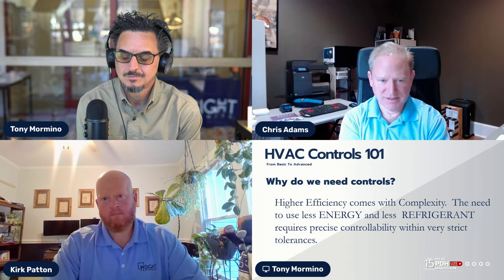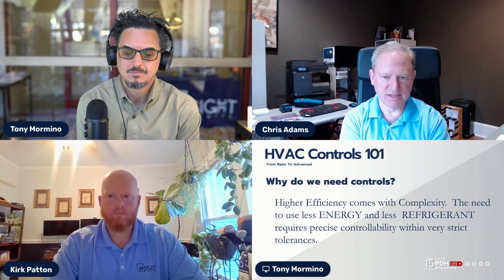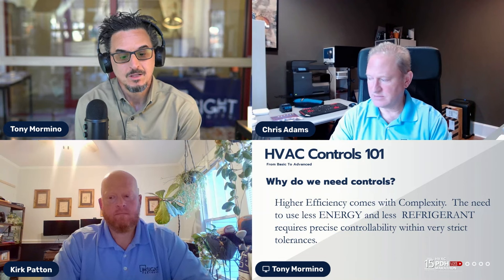On the refrigerant side, systems rely on the phase change of refrigerants to carry BTUs. With reduced refrigerant charges, the system must be very precise about exactly where that phase change occurs—liquid refrigerant must be stored in specific locations and gas in others. Modern controls are necessary to manage this precisely. The result is that even dehumidification equipment with hot gas reheat, which can seem overly technical, requires all those components to do what it does.